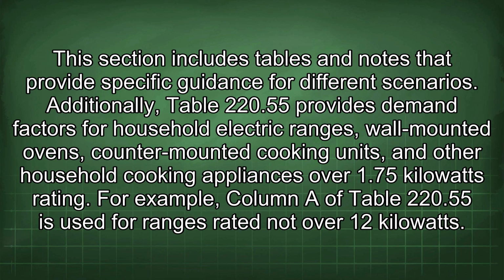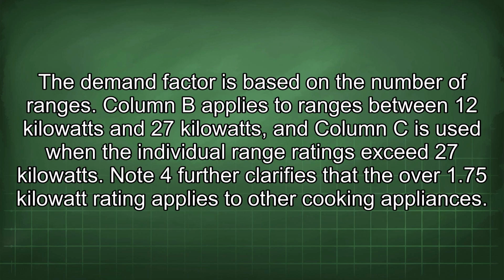For example, column A of Table 220.55 is used for ranges rated not over 12 kilowatts. The demand factor is based on the number of ranges. Column B applies to ranges between 12 kilowatts and 27 kilowatts, and column C is used when the individual range ratings exceed 27 kilowatts. Note 4 further clarifies that the over 1.75 kilowatt rating applies to other cooking appliances.